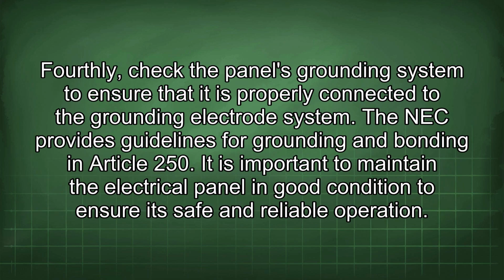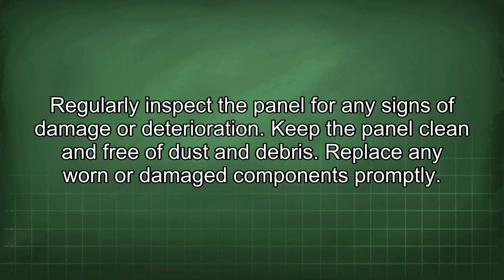Fourthly, check the panel's grounding system to ensure that it is properly connected to the grounding electrode system. The NEC provides guidelines for grounding and bonding in Article 250. It is important to maintain the electrical panel in good condition to ensure its safe and reliable operation. Regularly inspect the panel for any signs of damage or deterioration. Keep the panel clean and free of dust and debris. Replace any worn or damaged components promptly.